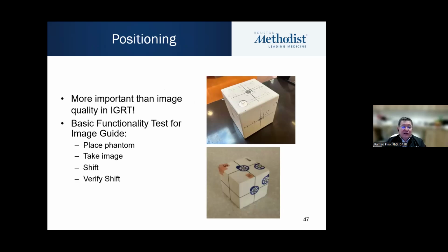I believe that positioning is more important than image quality in IGRT. Of course, if you cannot see the target, it's very difficult to make any guidance. But typically, we use relatively high dose gradients for treatment. So any small errors in positioning will translate into significant changes in the dosimetry of your target, especially in the era when we use very tight margins to treat patients. So typically, we test that daily, very important. We place a phantom, we take images, we apply shifts, and we verify the shifts.